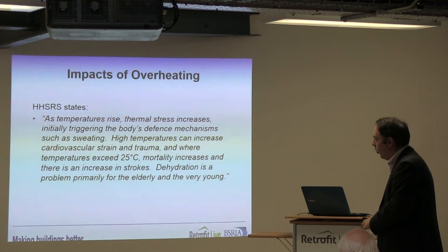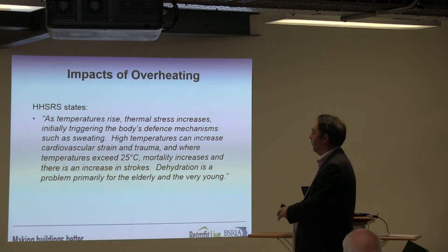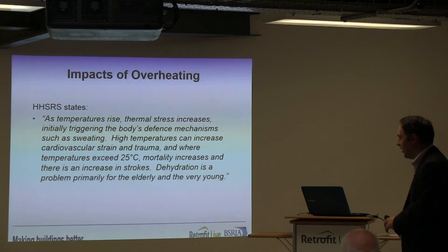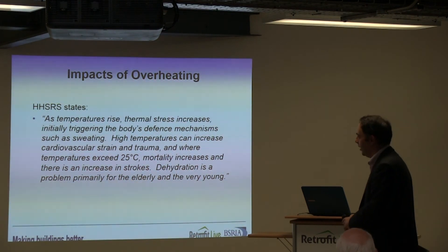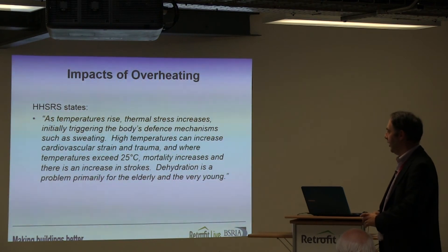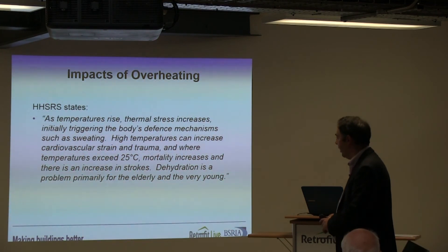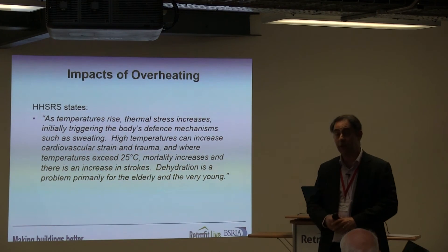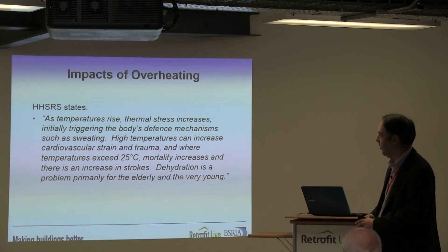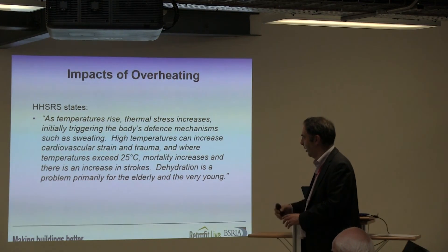How do we actually define overheating and what are the impacts associated with it? The Housing Health and Safety Rating System suggests that as temperatures rise, thermal stress increases, initially triggering the body's defence mechanisms such as sweating. High temperatures can increase cardiovascular strain and trauma. Where temperatures exceed 25°C, mortality increases and there is an increase in strokes. Dehydration is primarily a problem for the elderly and the very young. That kind of definition sets the criteria for environmental health officers when they look at housing as to what may constitute overheating.